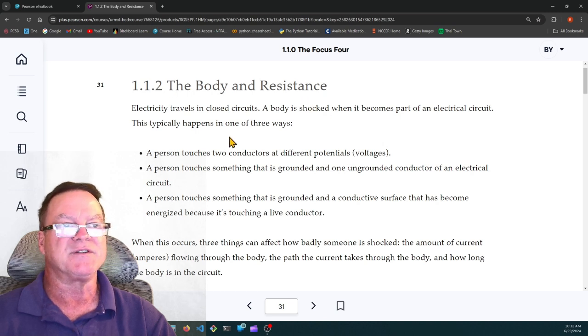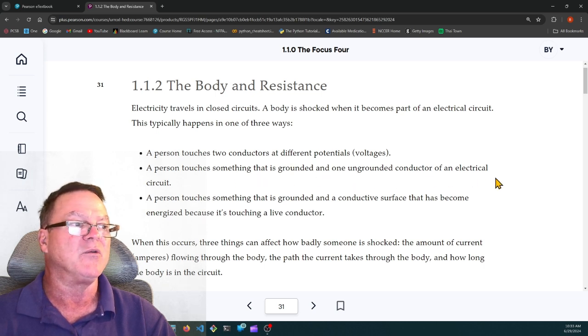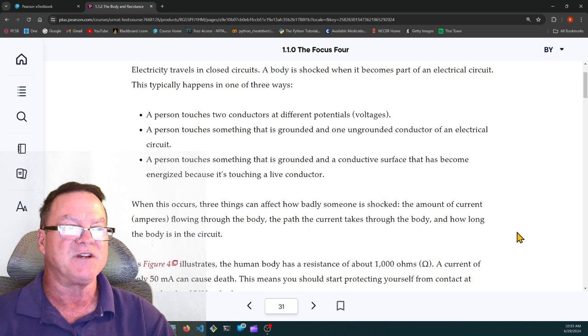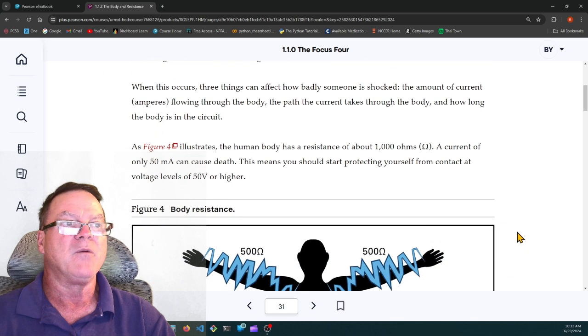1.1.2, the body and resistance. Electricity travels in closed circuits. A body is shocked when it becomes part of an electrical circuit. This typically happens in one of 3 ways: a person touches 2 conductors at different potentials; a person touches something grounded and 1 ungrounded conductor of an electrical circuit; or a person touches something grounded and a conductive surface that has become energized because it's touching a live conductor. When this occurs, 3 things affect how badly someone is shocked: the amount of current flowing through the body, the path the current takes through the body, and how long the body is in the circuit.